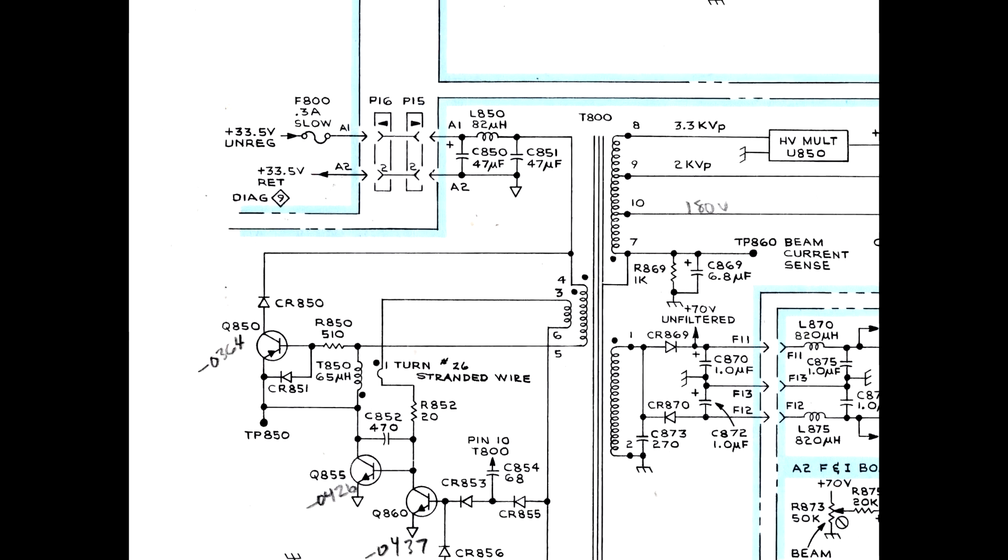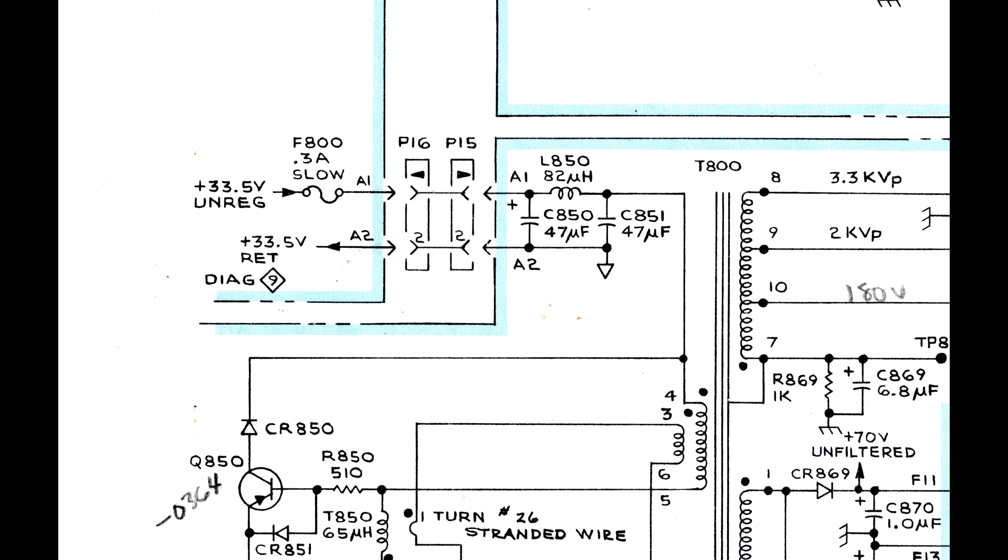A common cause for blowing this fuse is a short in C850 or C851, which, in conjunction with L850, provide a filter to prevent noise from the high frequency high voltage supply from feeding back into the power module plus 33 volts supply, and possibly to other plug-ins.